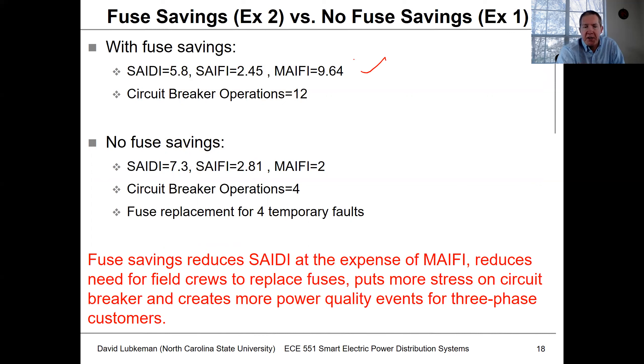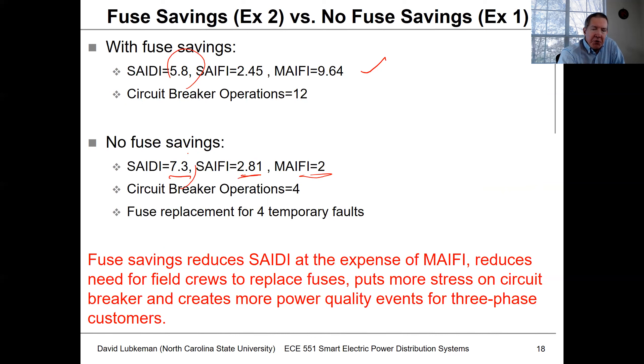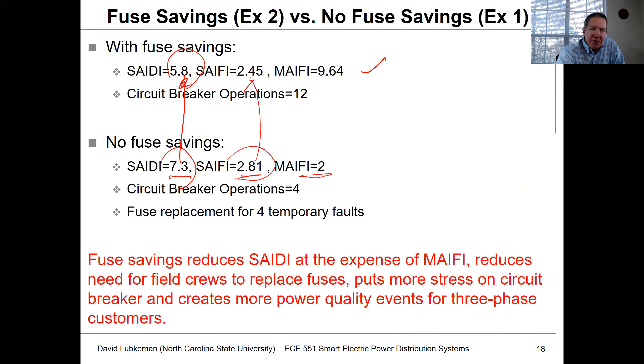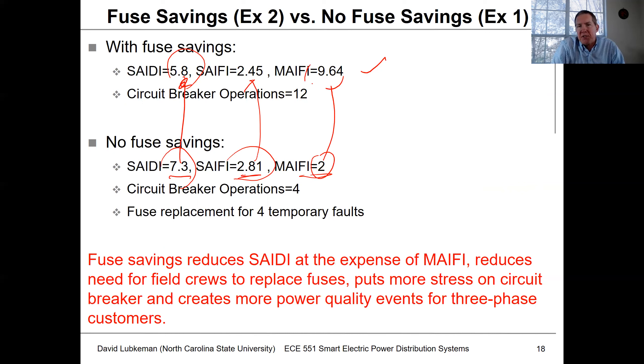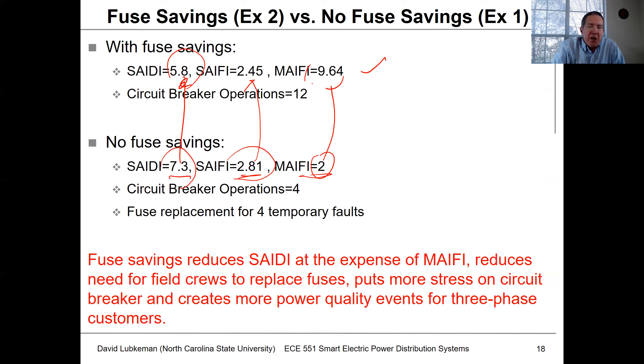Comparing to the part one lecture scenario with no fuse savings, SAIDI was 7.3, SAIFI was 2.81, and MAIFIE was 2. With fuse savings, we improve our SAIDI number noticeably, and SAIFI drops a little. The trade-off is that we're getting a lot more momentary events — more MAIFIE events on the circuit.